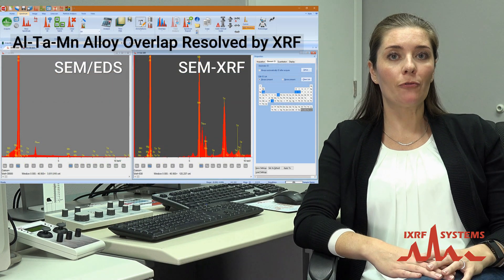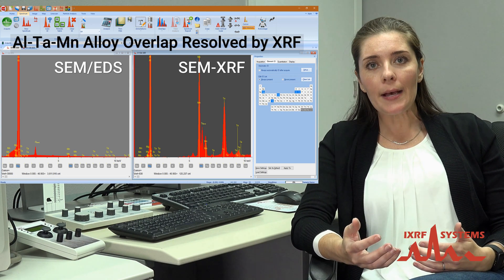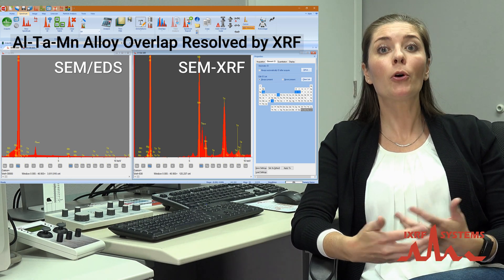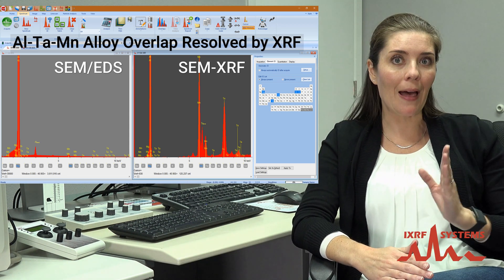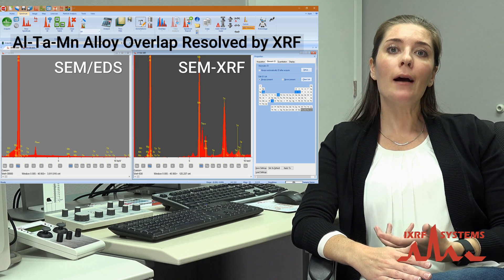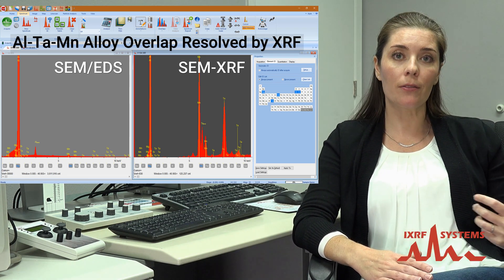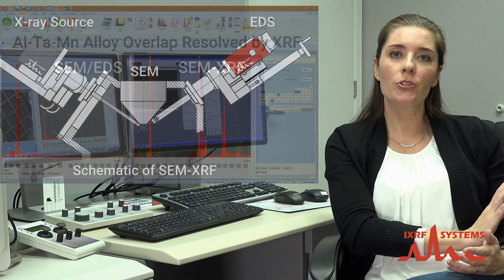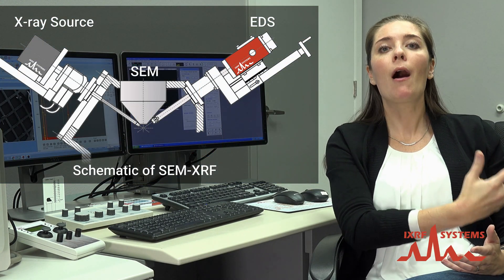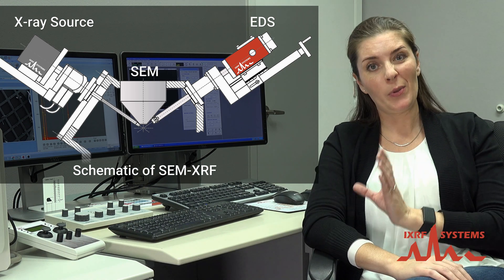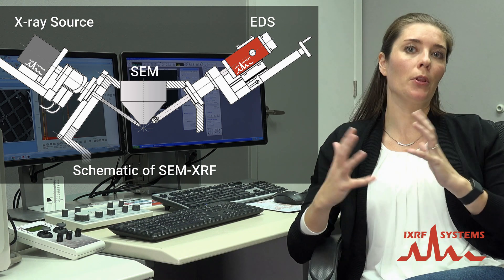Also, elemental overlaps. If we think of some of our heavier elements, with EDS we're stuck trying to identify multiple heavy elements in the lower energy region where they all overlap and sit on top of each other. But with XRF, we have much higher energy — we can actually excite those heavier elements at the higher end of the energy spectrum and get really nice peaks, with confidence in identifying those elements as indeed present, rather than being stuck trying to figure out a blob of peaks at the lower energy. A perfect example would be molybdenum, lead, and sulfur — low energy, big blob — but if we hit it with XRF, we can easily resolve and see those lead and molybdenum peaks, so now we know for sure we have those elements in our sample.